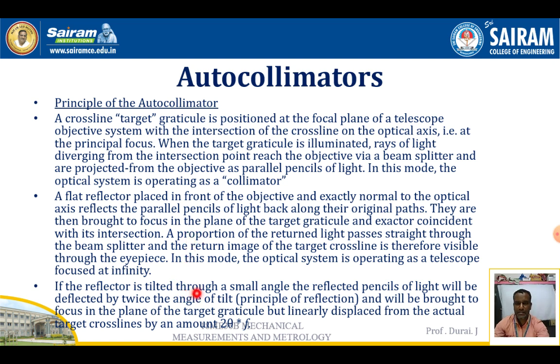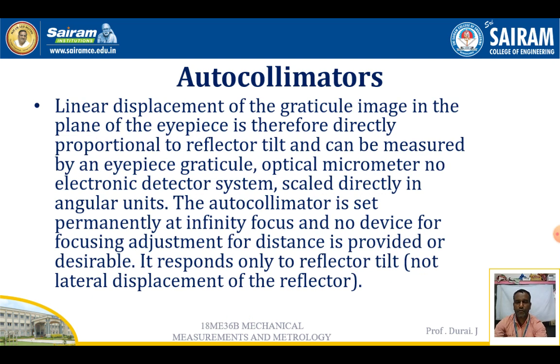If the reflector is tilted through a small angle, the reflected pencil of light will be deflected by twice the angle of tilt, and will be brought to focus in the plane of the target reticle, but linearly displaced from the actual target cross lines by an amount of 2 theta times the focal length. So in the autocollimator, the linear displacement of the reticle image in the plane of the eyepiece is directly proportional to the reflector tilt and can be measured.